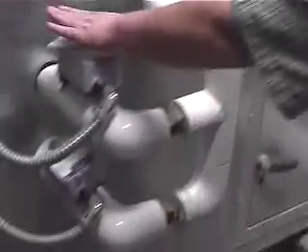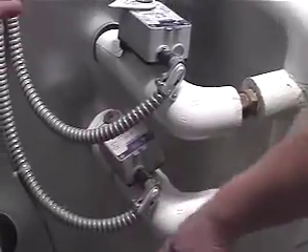What happens then, we open the drain valve, shut the makeup, and allow the pan to drain down for 15 minutes. After that, we open the flush valve and keep the drain valve open. The flush valve is there to clean the pan out, to get whatever media has dropped out, just to flush the pan. That stays that way for an additional 15 minutes, I believe. And all these times are adjustable. After that, flush will shut, drain will stay open, and then we just allow the media to dry out for about another half an hour or so, and then the unit would shut down.